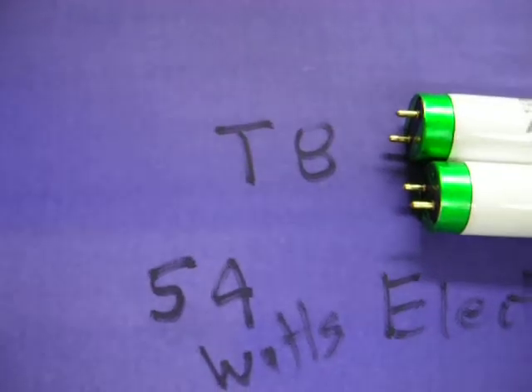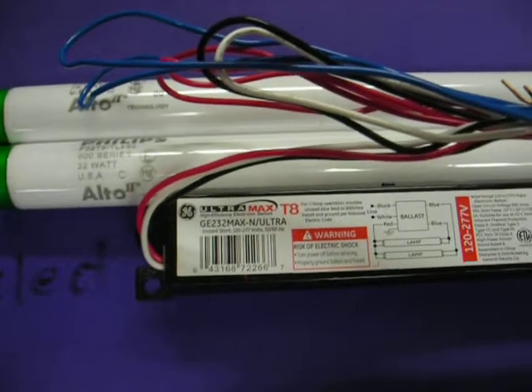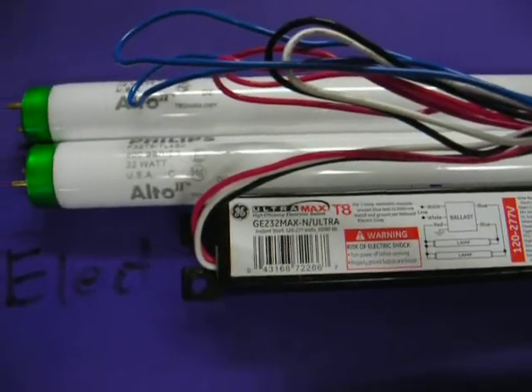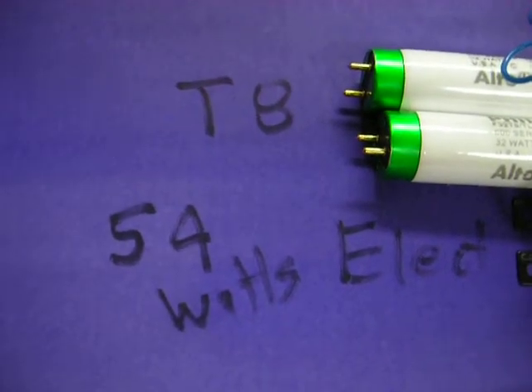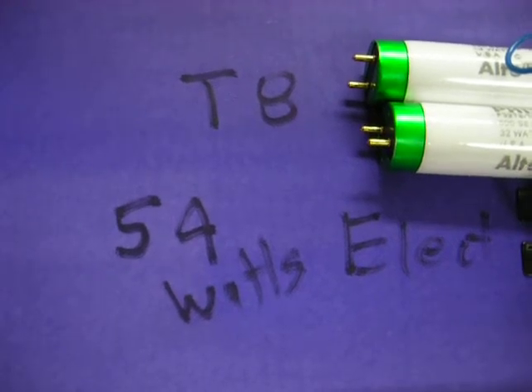With the small diameter little guys — T8s — we measured 54 watts, and that's with an electronic ballast. All three of those are with bulbs and measured input power with a Kill A Watt meter, measuring the input power to the actual ballast.